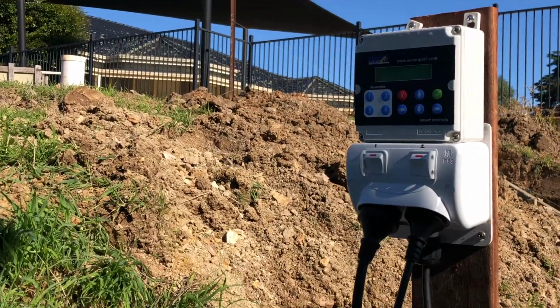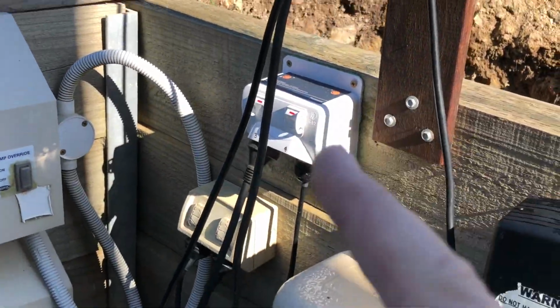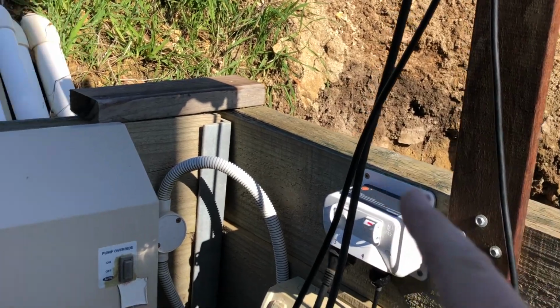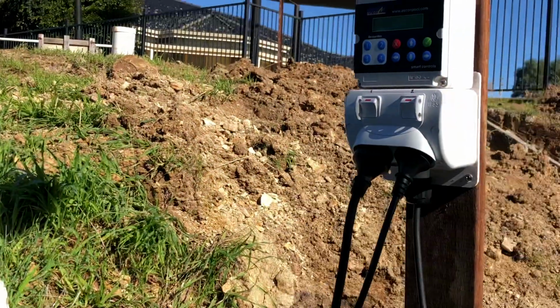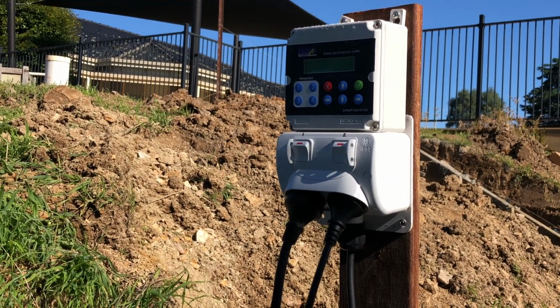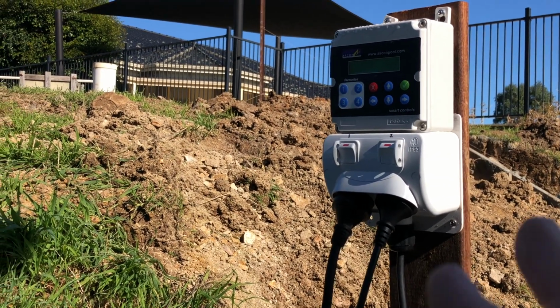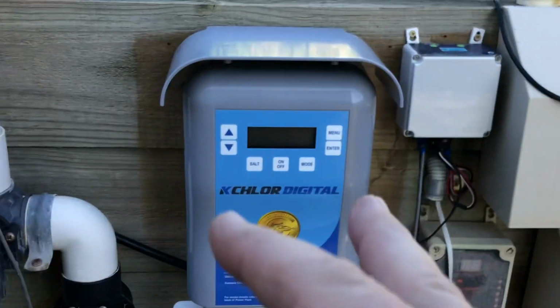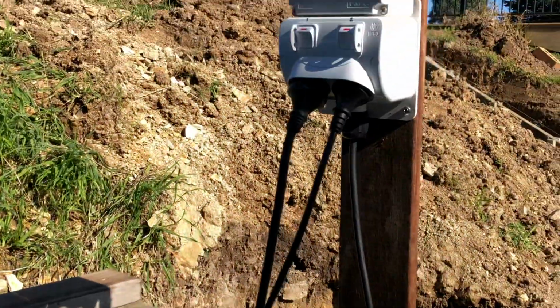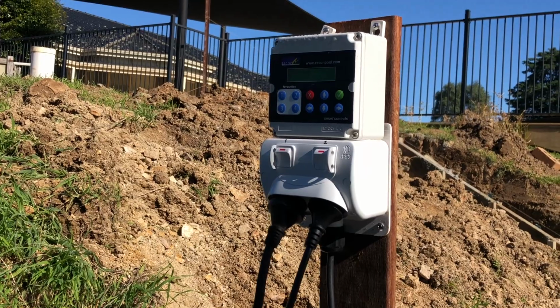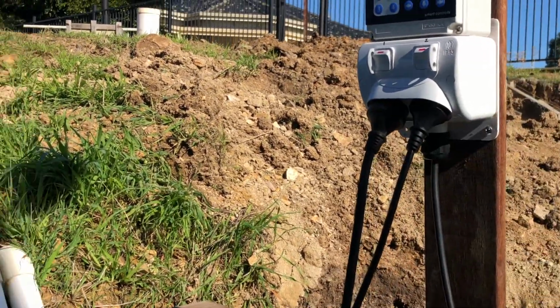So again, we've got the main controller there, the second power point there. Now these two can talk to each other, as also we've got this one driving valves. You see the motorized valves here and here. This is actually running that, and that's through the controller as well. We've got a group going on this one. So when you press a button, it turns the heater on, it turns the valves, so it goes to spa only, and runs it to heat the spa. So you've got a button which does multiple things. That's where your groups come in.